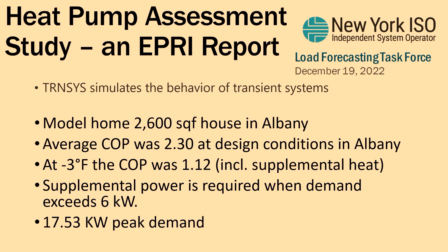Now, how is that looking in the field studies? Well, we had a couple of field studies here. This is the CAPMA study, which you can download on the NY-GEO web page. Same in-field performance, average 2.25, like okay, and an average outside temperature of 17 degrees. The average demand was 2.77 on that site. However, the maximum was 17. Wow. This is field data now. And that did not even include the resistance demand in there.